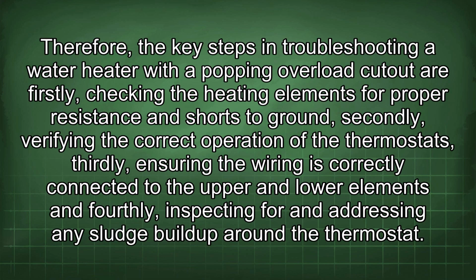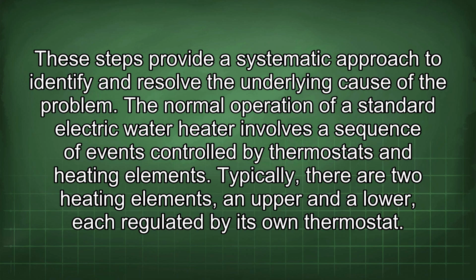Therefore, the key steps in troubleshooting a water heater with a popping overload cutout are firstly, checking the heating elements for proper resistance and shorts to ground. Secondly, verifying the correct operation of the thermostats. Thirdly, ensuring the wiring is correctly connected to the upper and lower elements. And fourthly, inspecting for and addressing any sludge built up around the thermostat. These steps provide a systematic approach to identify and resolve the underlying cause of the problem.